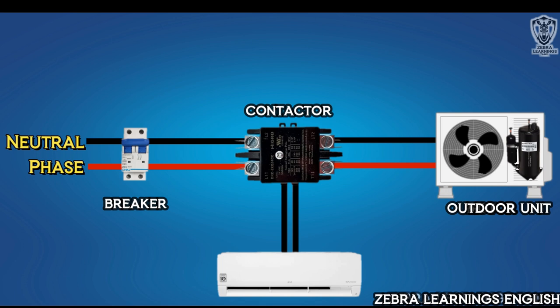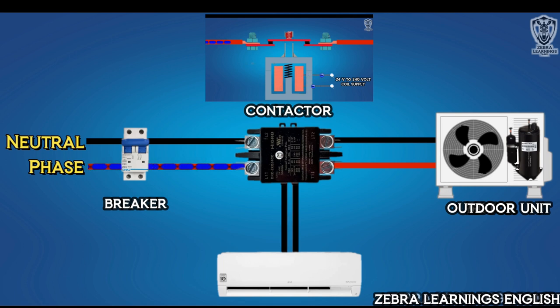Similarly, AC unit also gives power supply to outdoor unit through contactor. When the room temperature is high, the PCB in the indoor unit sends a 24-volt power supply signal to the contactor. Through this, contactor energizes and power supply flows. Compressor and fan motor start running.